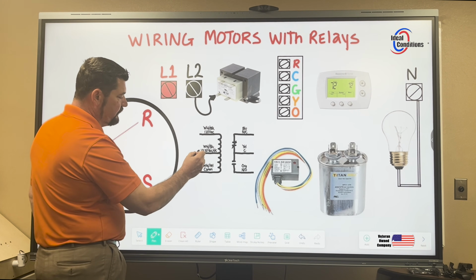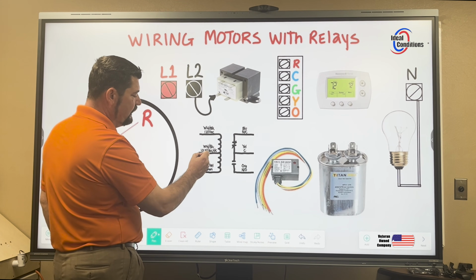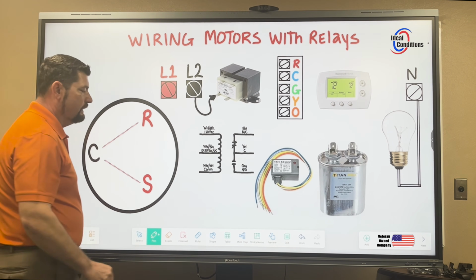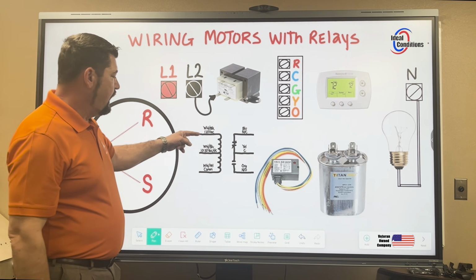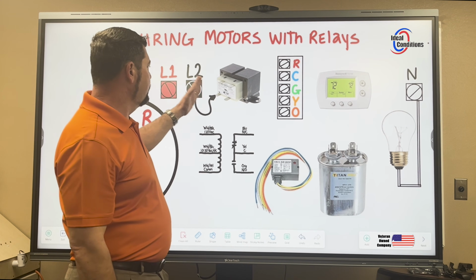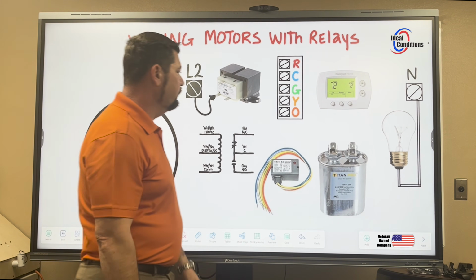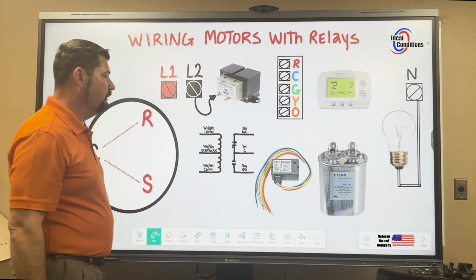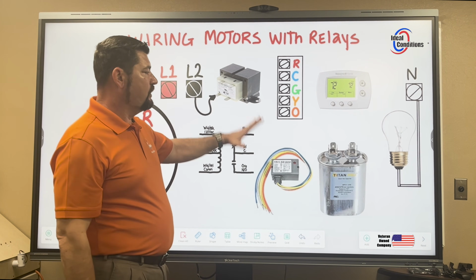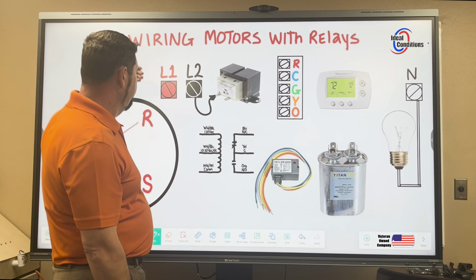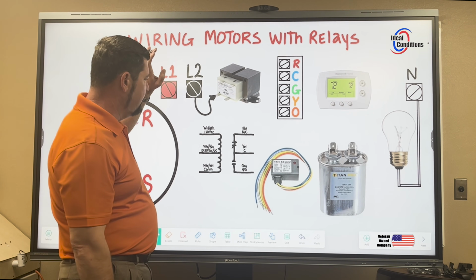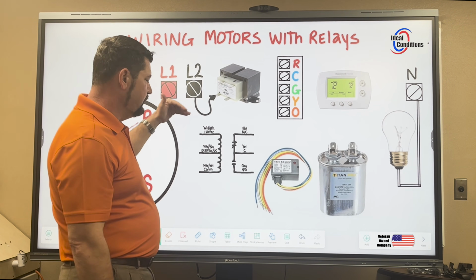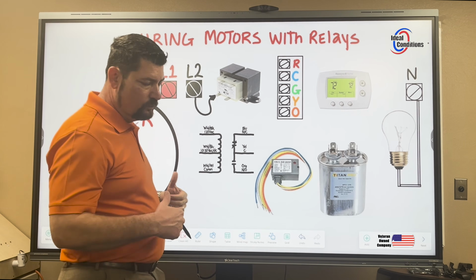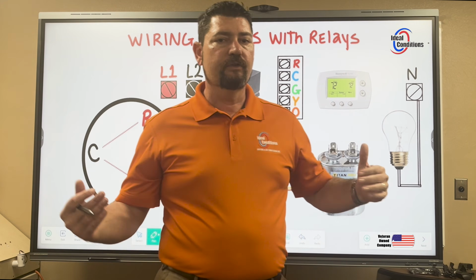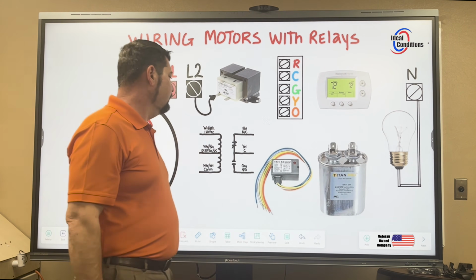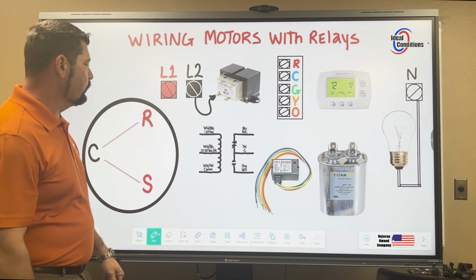or I can feed it 10 to 30 volts direct current, or 10 through 30 volts alternating current. Now, in this application, I do have 120 volts between any one of these two legs and neutral. So we're going to take advantage of that just to show you what that will look like. But I don't have any direct current here. I would have to put another transformer in here to step down voltage to get that DC, and again, we'd be here for 90,000 hours. We're trying to get through how we simply wire this up as a blower relay.